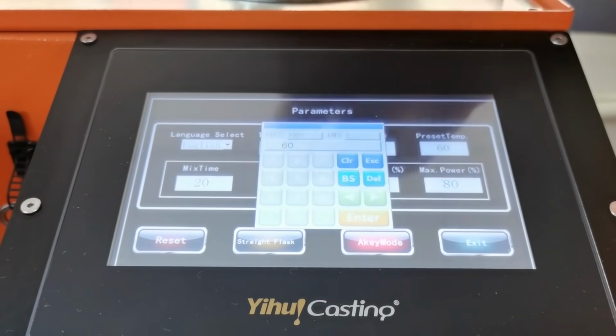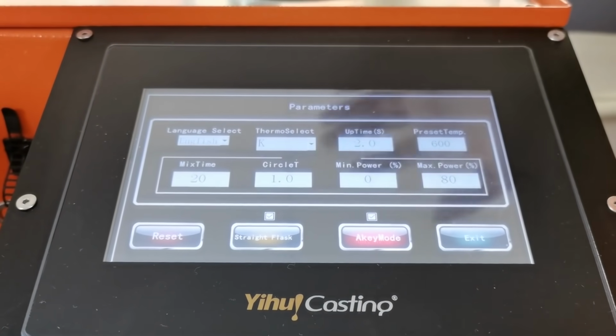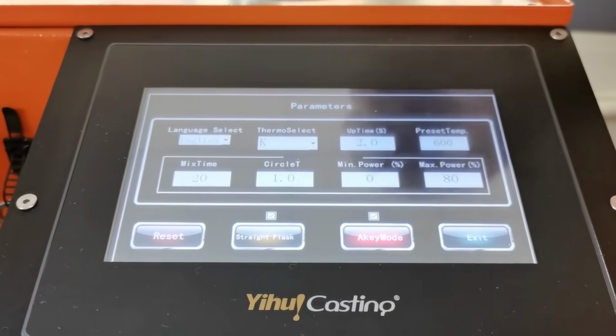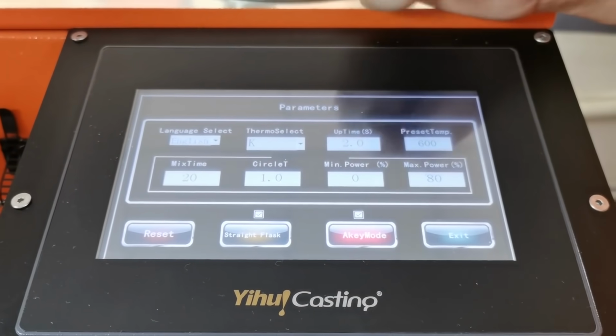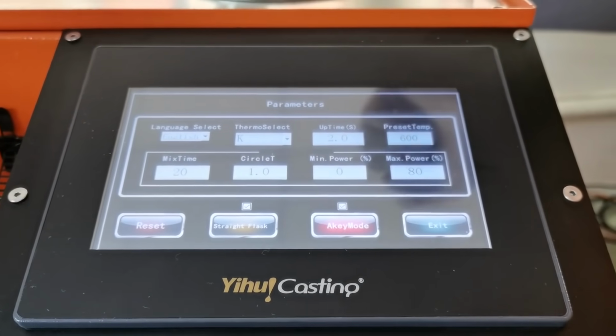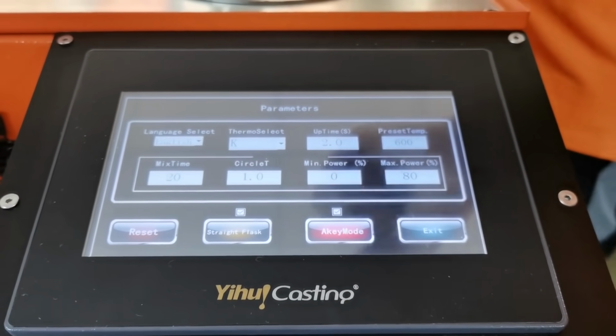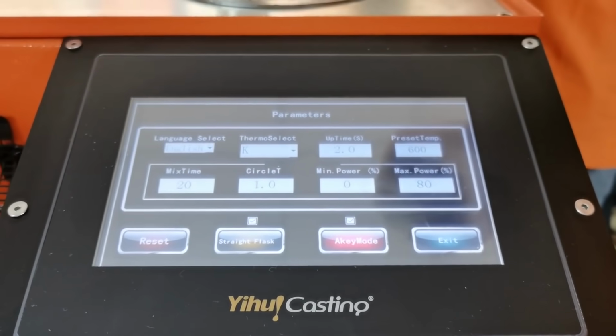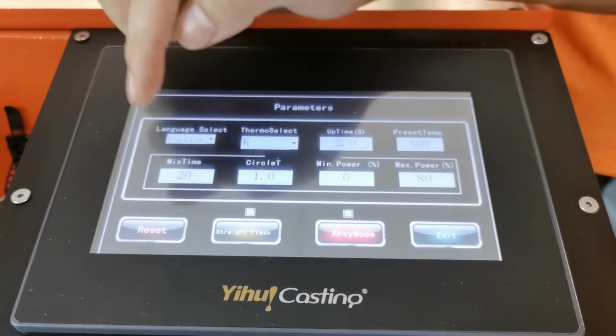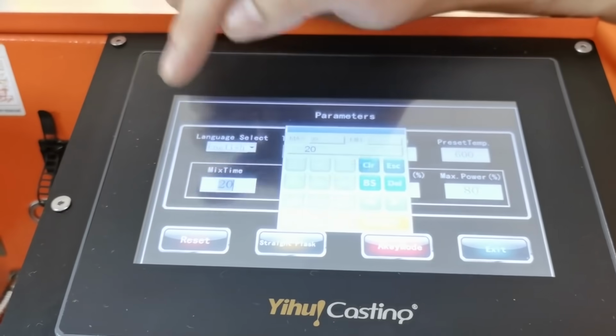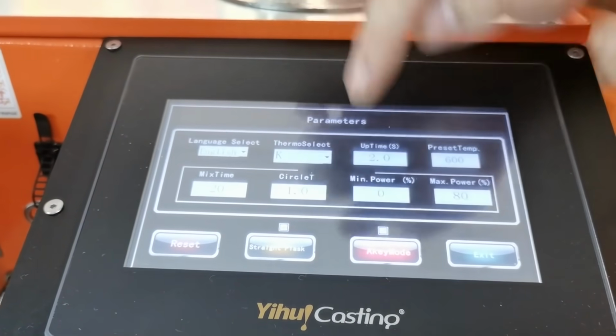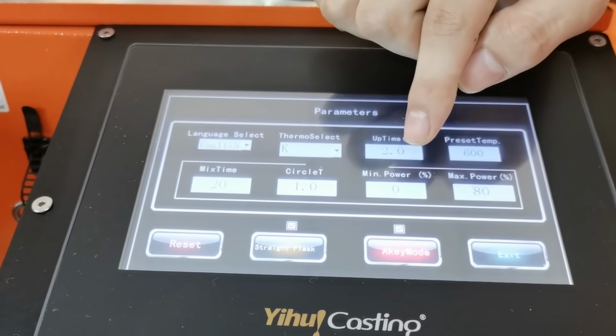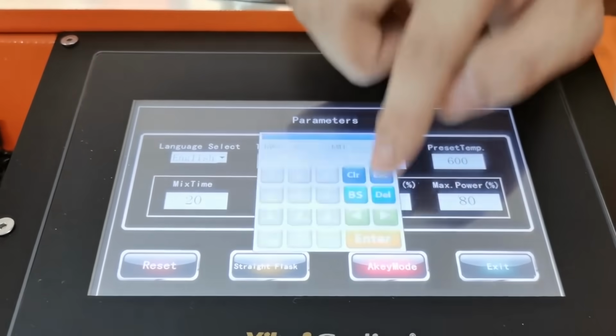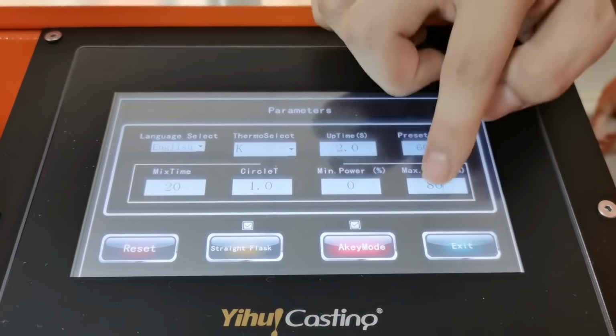Okay, then the preset temperature. For this part, we set 600 degrees. But actually for this part, the max temperature we can set is 800 degrees. But the higher the temperature you set, the faster the crucible will oxidize. So we recommend you set 600 degrees. Then the mix time. For mix time, we set 20 seconds. Okay, then the mini power and the max power. For the mini power, we set 0%. For the max power, we set 80%.